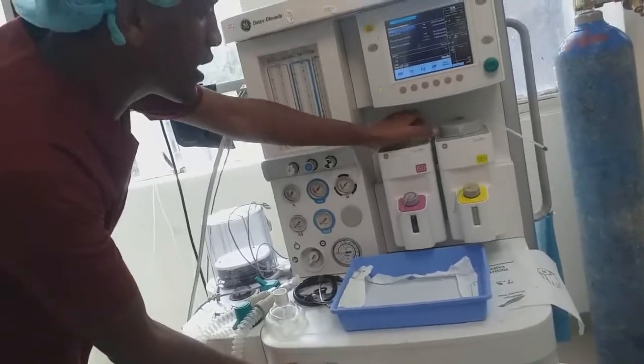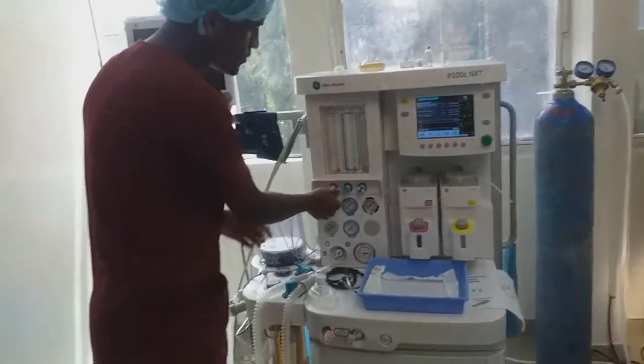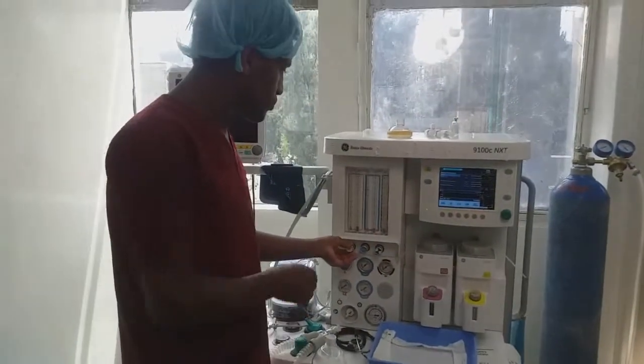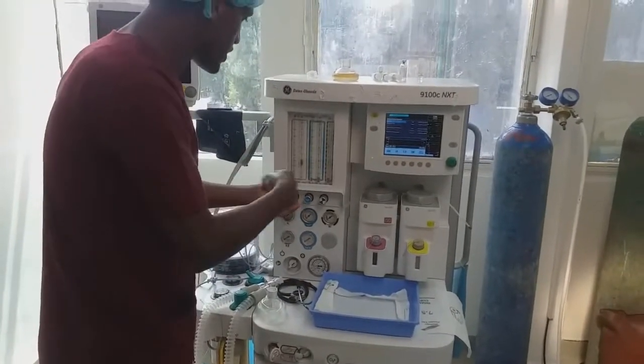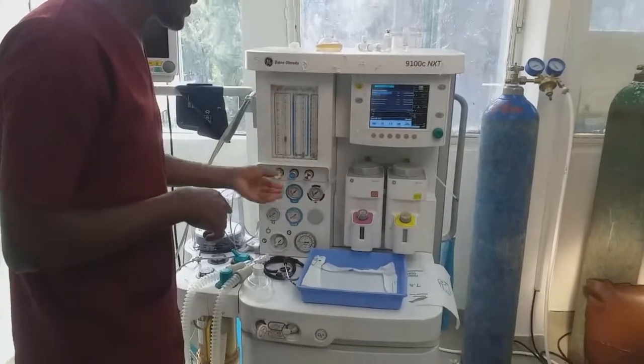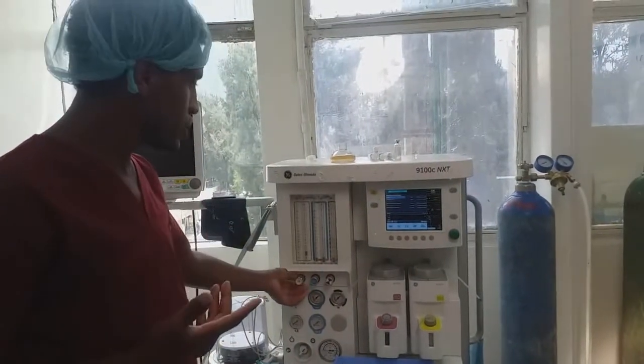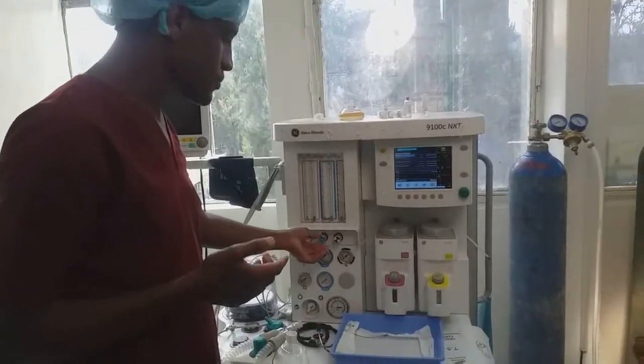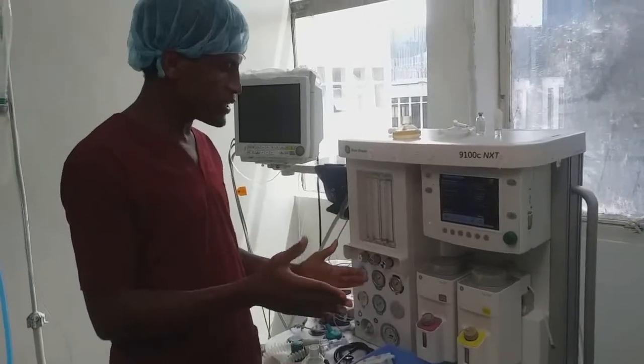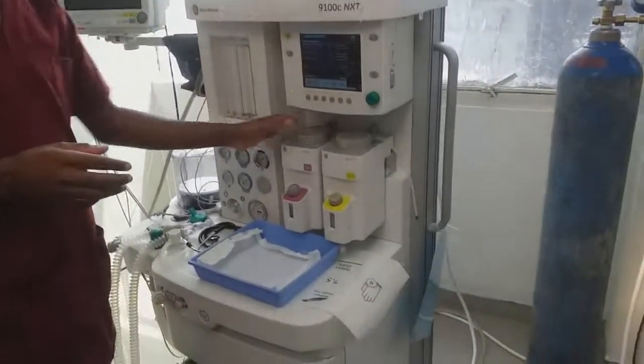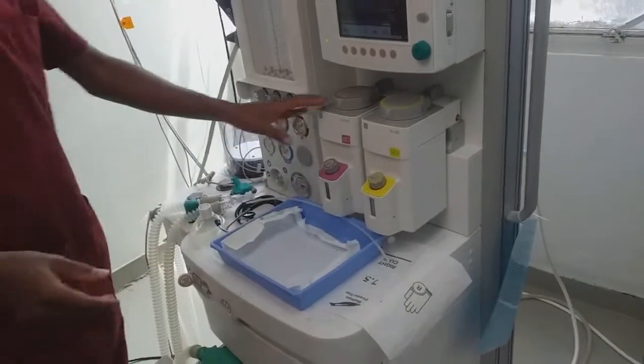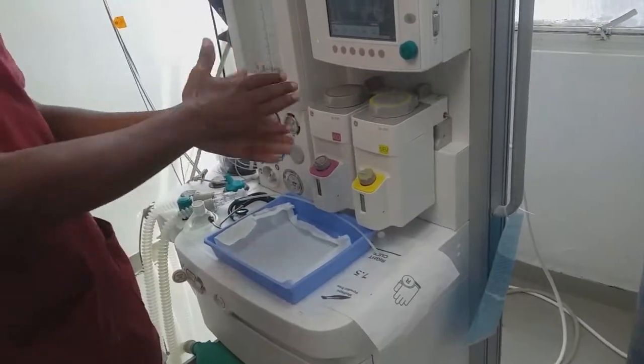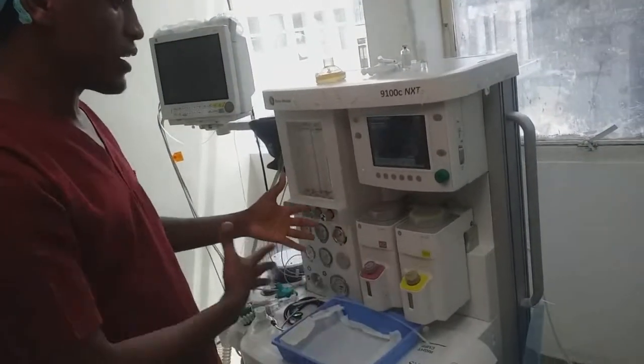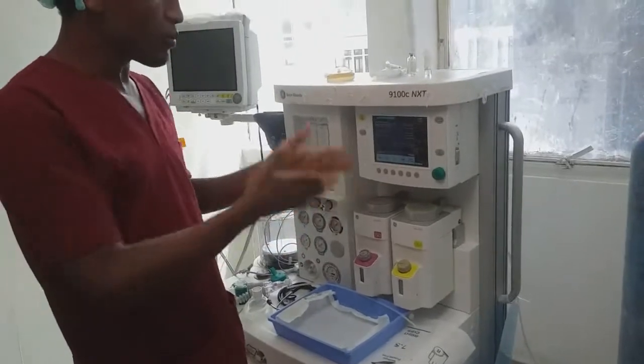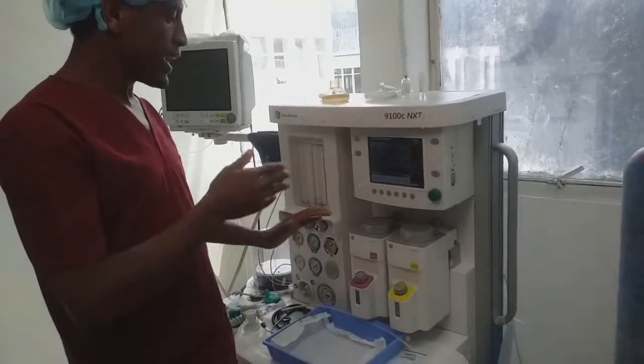I have done the low pressure system leak test now. We also observe the bobbin movement itself. Bobbin movement should be with normal pressure. The bobbin adjustment and movement should also be checked. In the vaporizer check test, we need to observe the proper arrangement. The position should be correct. If there is deviation from the normal position, the appropriate output will not be established. So the upright position is mandatory, and it should be appropriately filled.